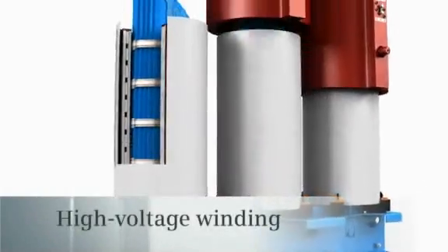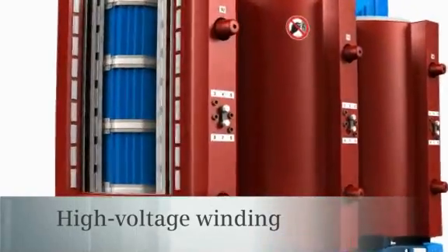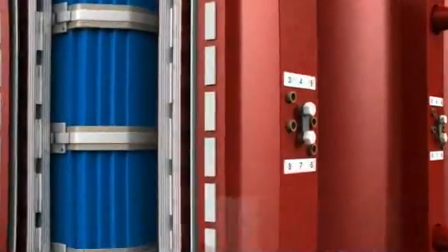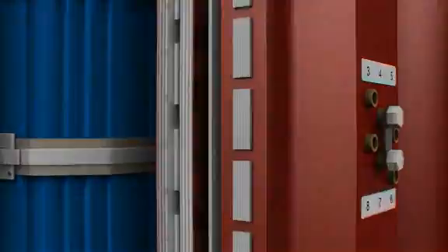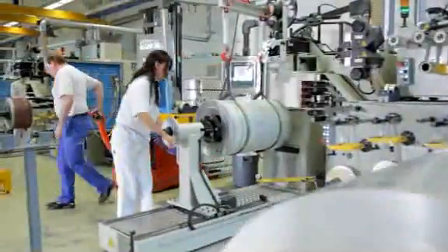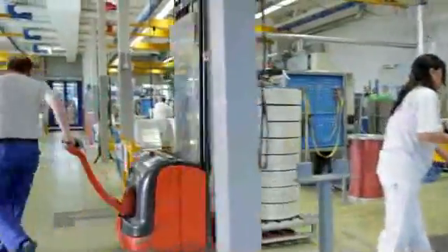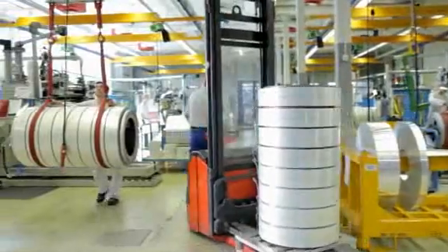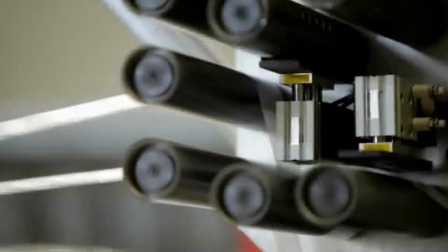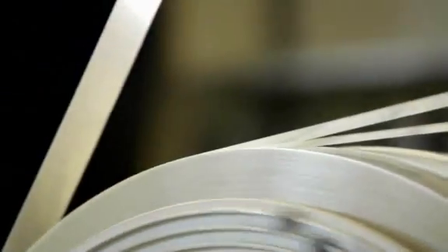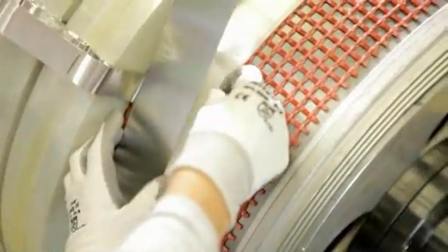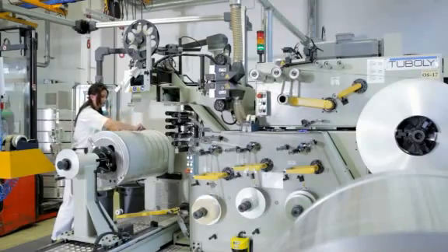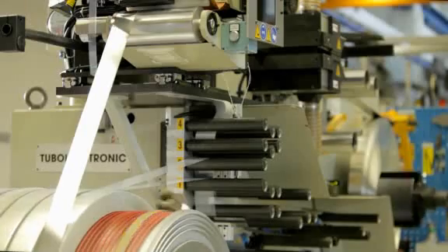The coil with the higher voltage and lower current is called the high voltage winding. It is formed of several parallel single foil type aluminium coils. Separated by two layers of highly temperature-resistant plastic foil, the metal strip is wound with precisely regulated tension. The work environment is user-friendly, clean and safe. This helps to avoid mistakes right from the start.